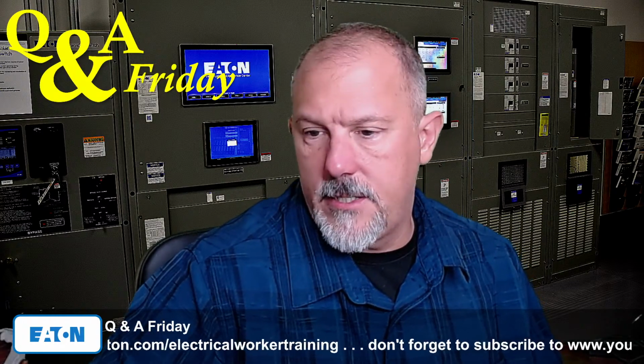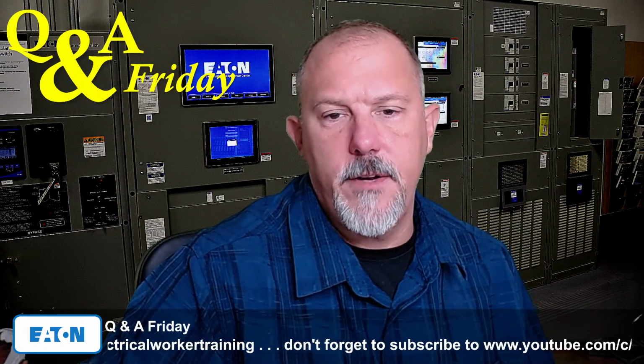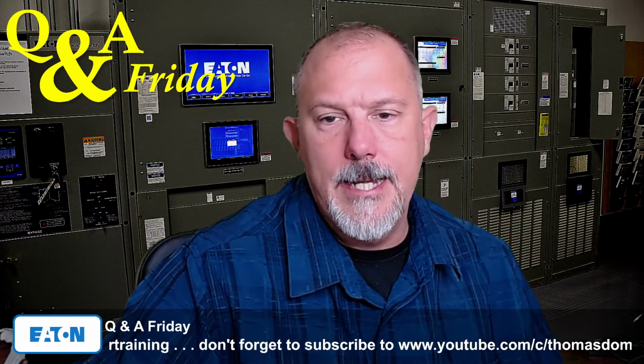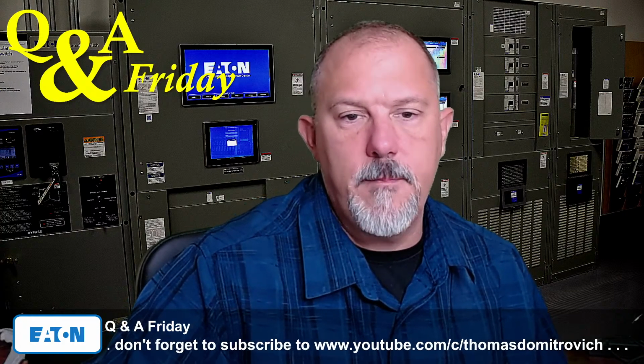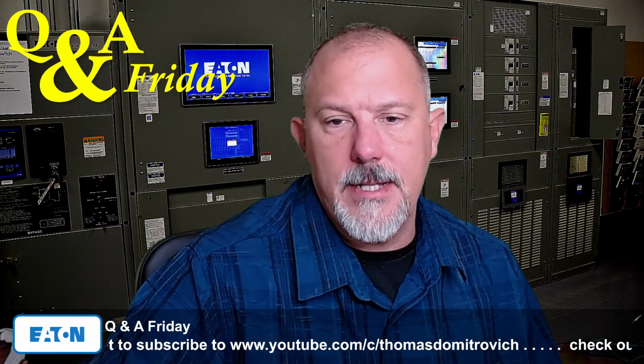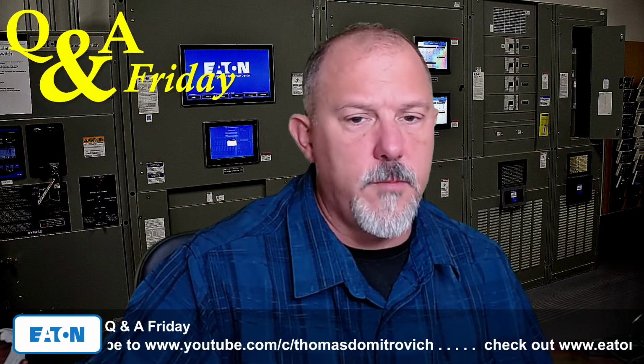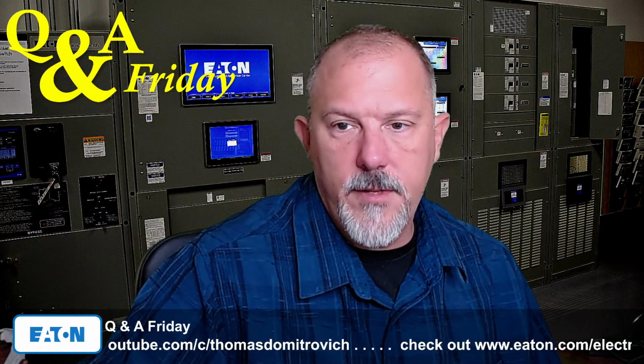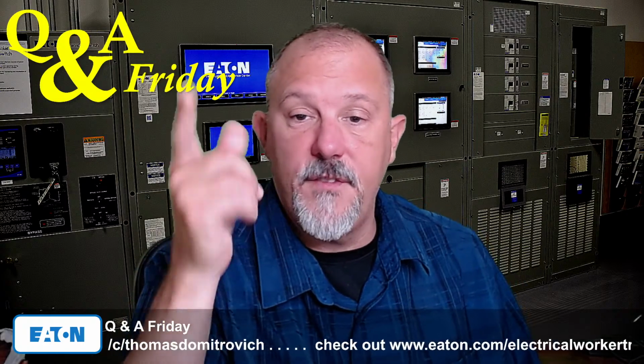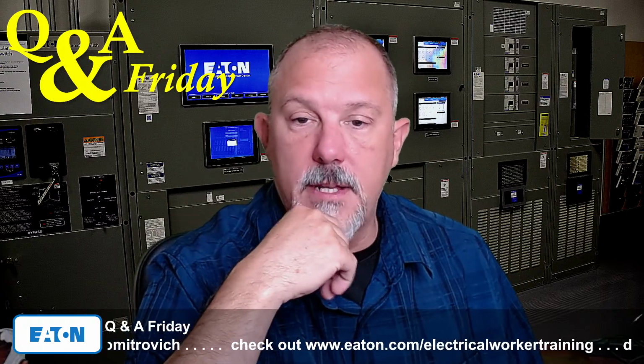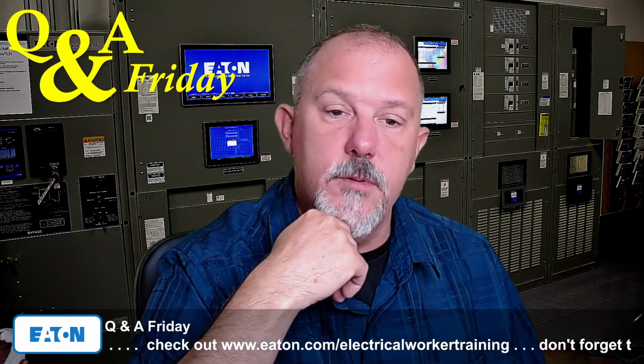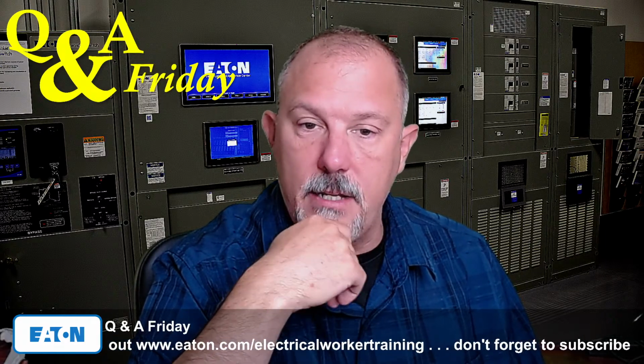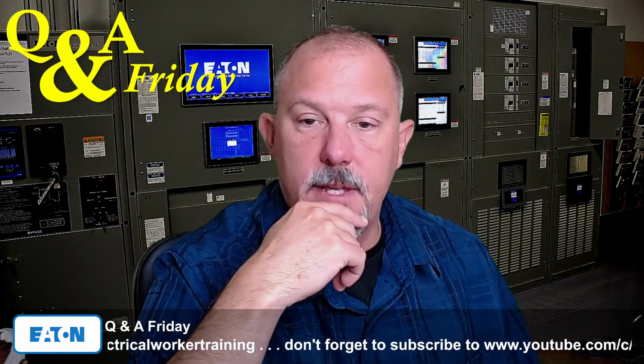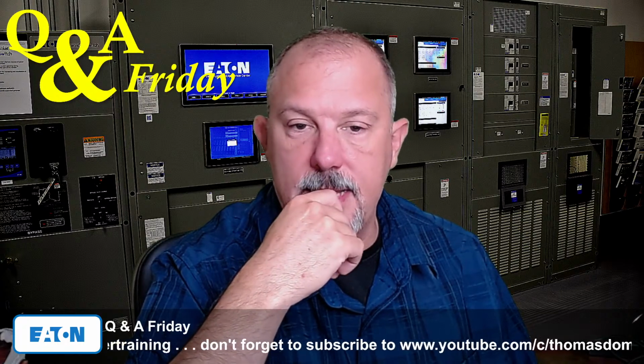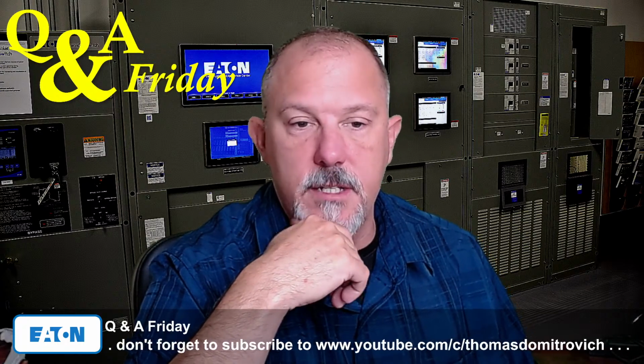I never really considered short circuit current ratings for every small piece of equipment before, and don't think I'm alone. In cases of many pieces of small equipment, it happens to have been listed and made for a typical installation, so there are normally no issues. However, and this is talking about short circuit current rating, the 15-minute tech talk I did, it would help the installation community be more aware if there was more standardizing of things and putting it into tables in the NEC or something. We can't afford to make people buy standard upon standard and publication upon publication.